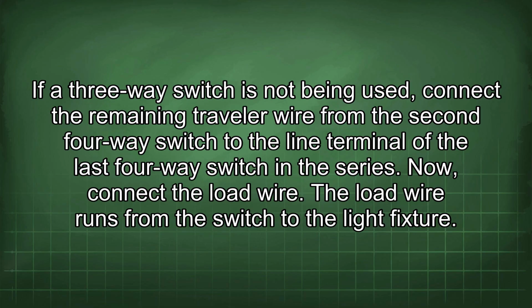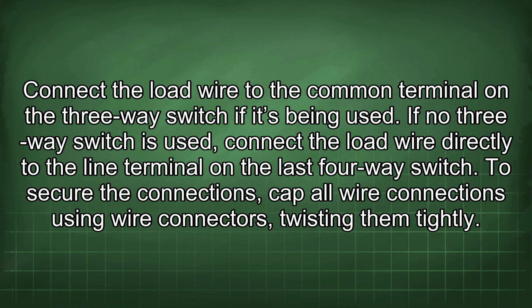Now connect the load wire. The load wire runs from the switch to the light fixture. Connect the load wire to the common terminal on the three-way switch if it's being used. If no three-way switch is used, connect the load wire directly to the line terminal on the last four-way switch.